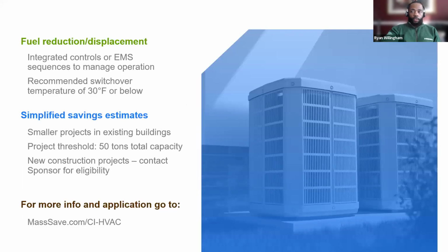So some key points to note: this is a fuel reduction or fuel displacement incentive. So we are paying for you to displace, again, natural gas, fuel oil, propane, or electric resistance. This is for partial displacing systems as well as full displacing systems. So if you are doing a partial displacement, we do require that you have an integrated control system so that you can automatically switch between the heat pump and the fossil fuel system whenever it's advantageous. We don't require a specific switchover temperature, but we do recommend that it's 30 degrees or below.